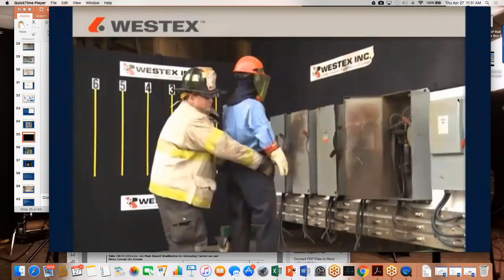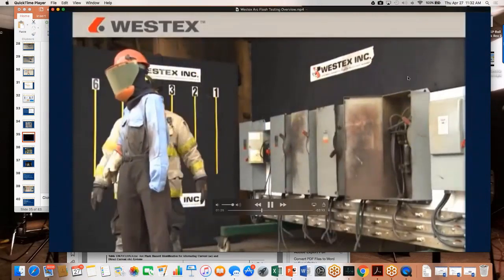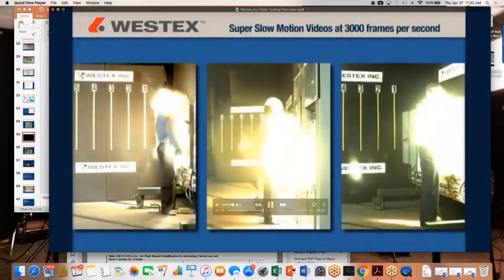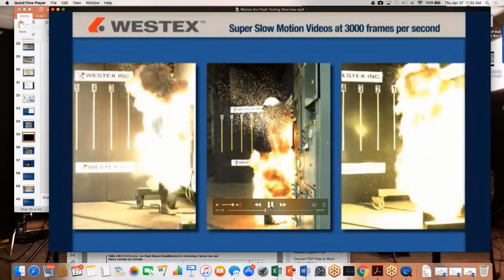As far as we're able to determine, the work of this test series is the first of its kind and scope in the world, and we're happy to be able to share it with you. This includes a new series of arc flash videos shot in super slow motion at 3,000 frames per second, which is 100 times slower than standard video.